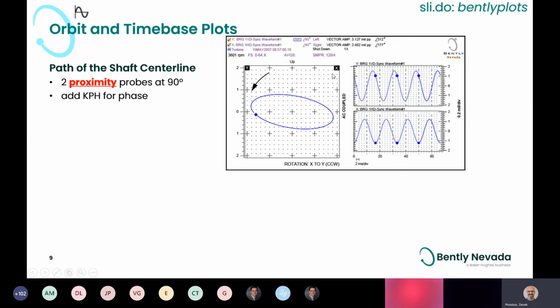Another observation about this is that these waveforms are very nice, clean sinusoidal waveforms. That's the first visual hint to us that this is probably a filtered signal. And if we go up to the header here, we can again see that this is for the 1x frequency. This is filtered 1x data. Another thing that tells us that this is 1x data is that the amplitudes are shown on the top here. You're getting amplitude and phase.